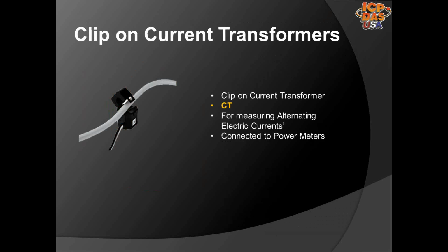Current transformers, abbreviated as CT, are used for measuring alternating electric currents. Current transformers isolate measurement instruments from high voltage and monitored circuits. A current transformer allows the production of a reduced current, which is accurately proportional to the current in the circuit. It can be connected to measurement devices like smart power meters. Data from smart power meters can be logged with data logger devices.